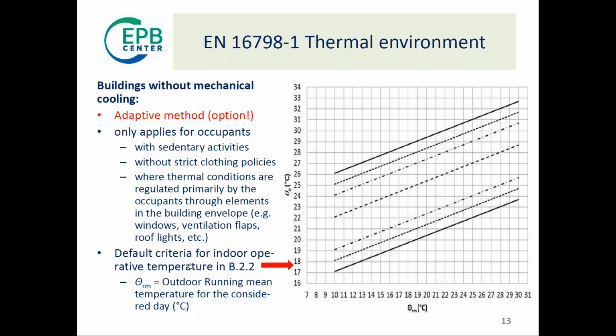So this adaptive model may allow for higher temperatures with high outdoor temperatures, as we can see here—it increases quite high when you don't have very strict limits for a category with moderate requirements. But again, it's only under these conditions. If you don't fulfill them—if you have a strict clothing policy, or no access to openable windows or similar things—you must not apply this model.